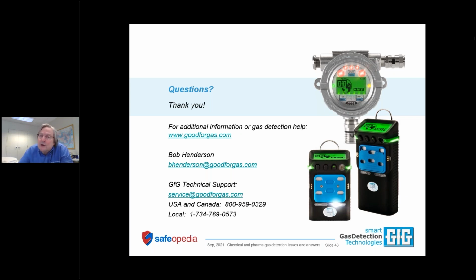It takes even more time if you have a standard catalytic sensor with a protective filter that's designed to remove silicone, which is one of the very worst of the combustible sensor poisons. So it really can take 5 or 6 or 7 minutes for even ethanol to get into the sensor to respond, and for your readings to stabilize. And that takes a long time. That's kind of too long. And then the other issue is that alcohol is very hard on the active bead in the sensor, especially methanol.